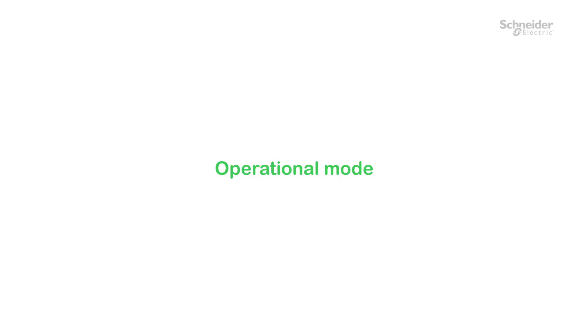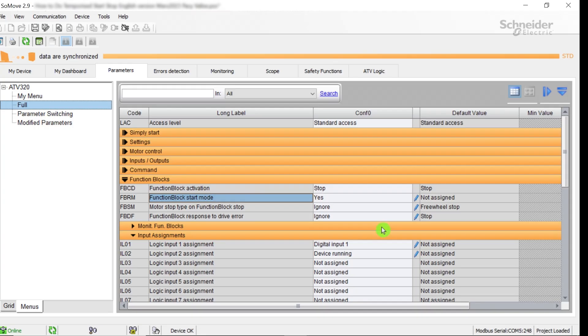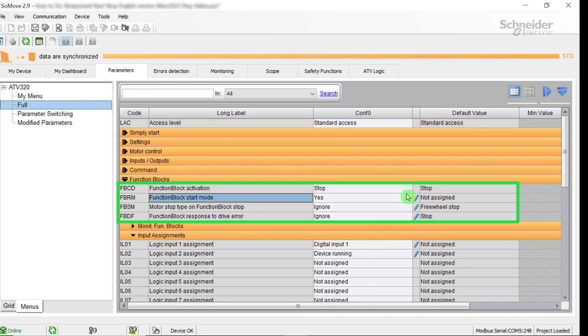Operational mode. The FBCD, FBRM, FBSM, and FBDF parameters in the Function Blocks tab manage the running mode of the ATV logic tasks in parallel of the drive application task.